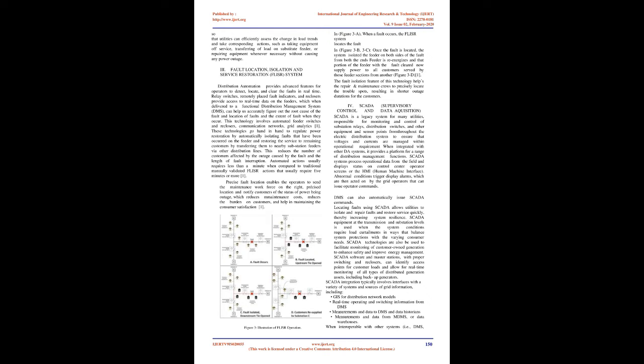Automated feeder switches and reclosers. Automated feeder switches open and close to isolate the faults and repair the feeder with the fault to restore power back to customers on line segments without a fault. They are typically configured to work with smart relays to operate in response to commands from an autonomous control system, distribution management systems, and signals from grid operators. Switches can be configured to close and open at predetermined intervals when fault currents are detected. This action is called reclosing of the switches, and they are deployed to sectionalize faulty sections of the feeders and to divert power around the faulty section of the feeder and re-energize only after the obstruction has been cleared by itself from the feeder line.